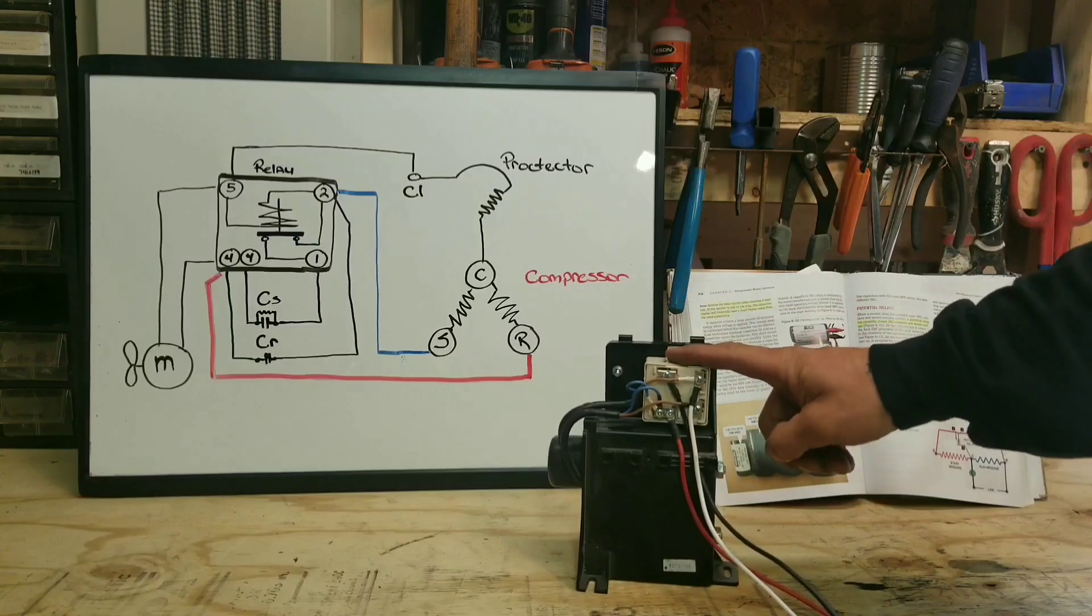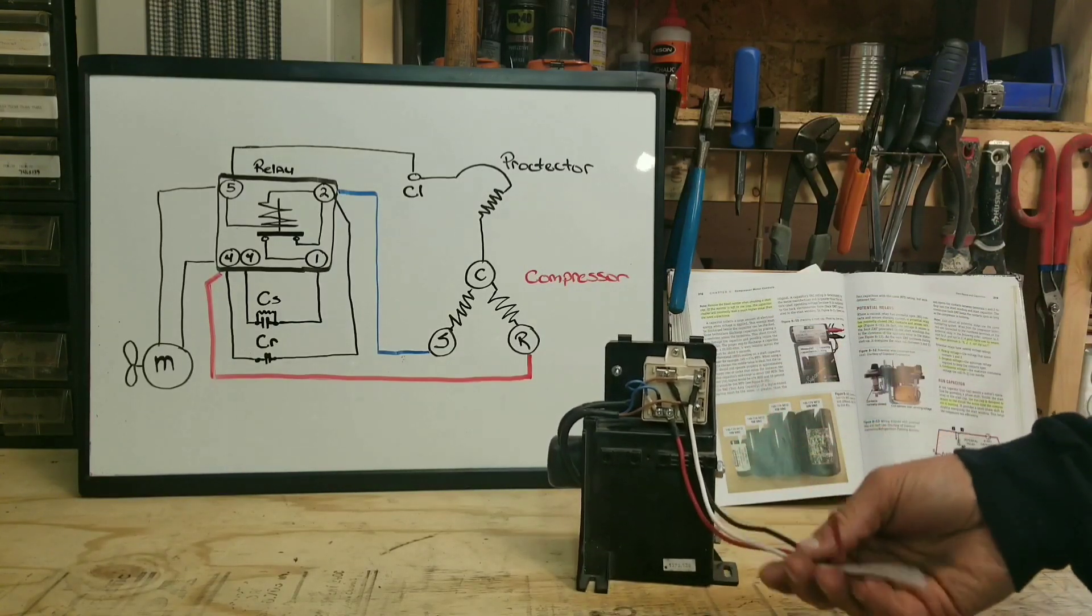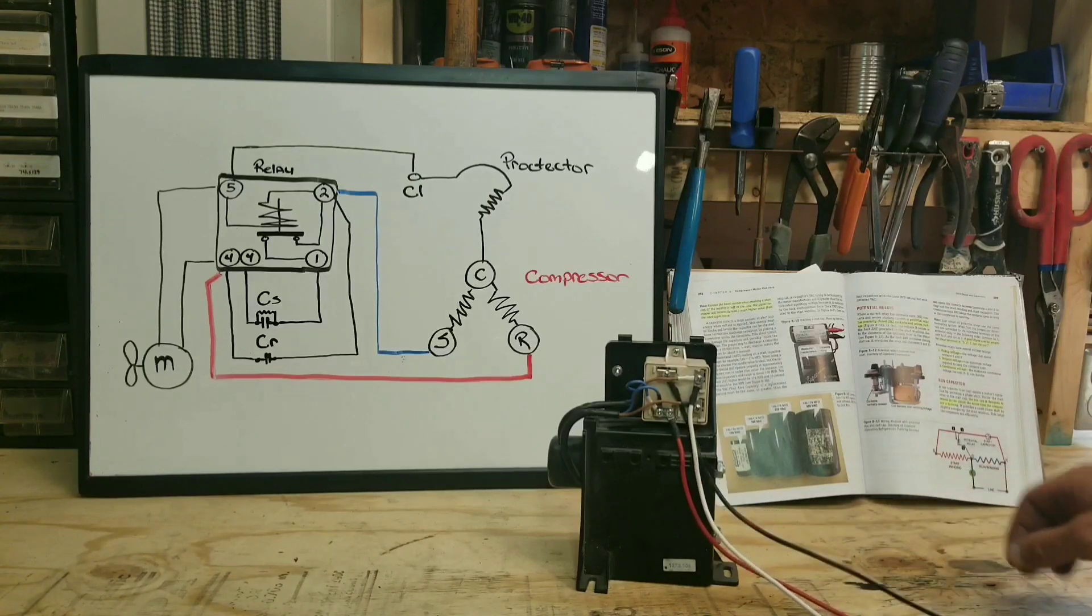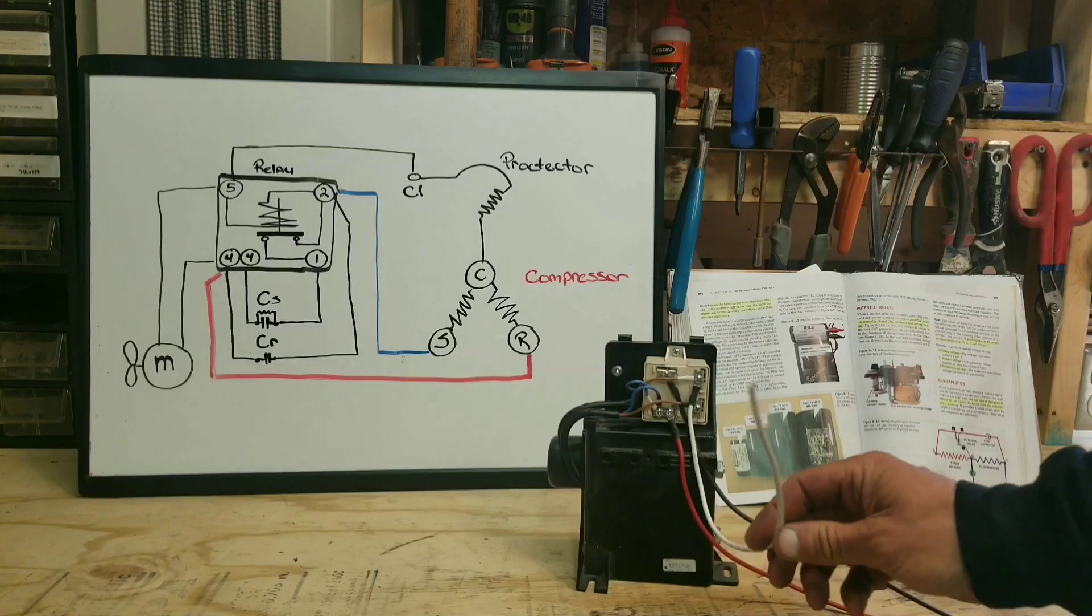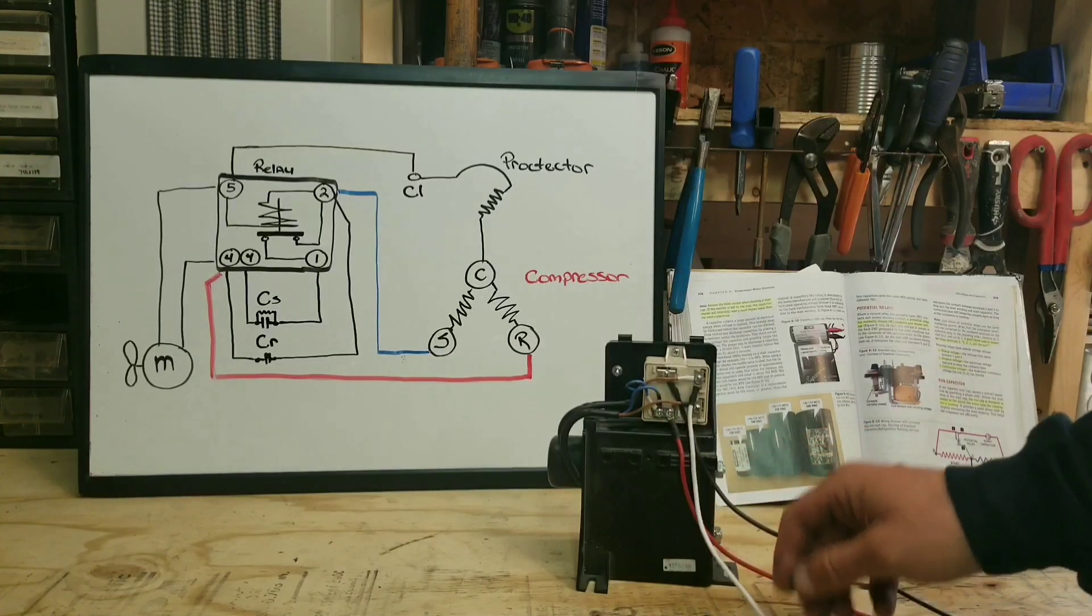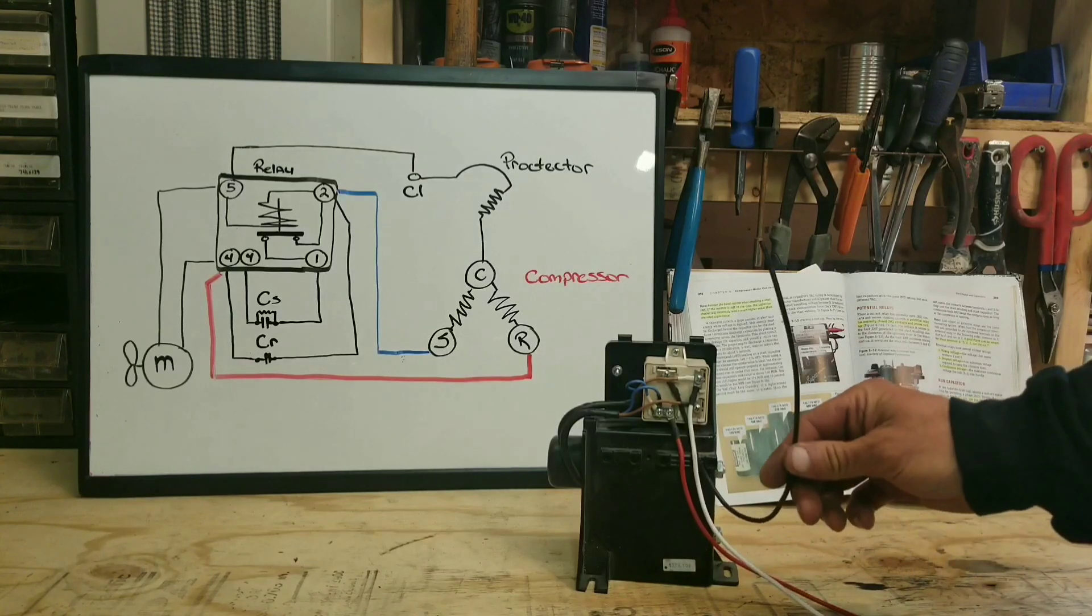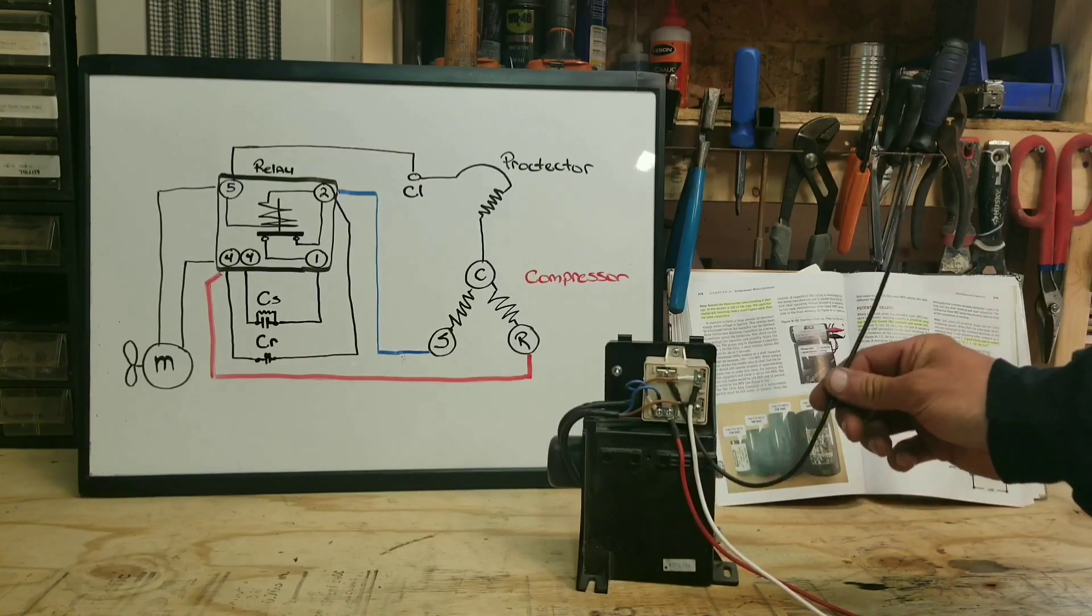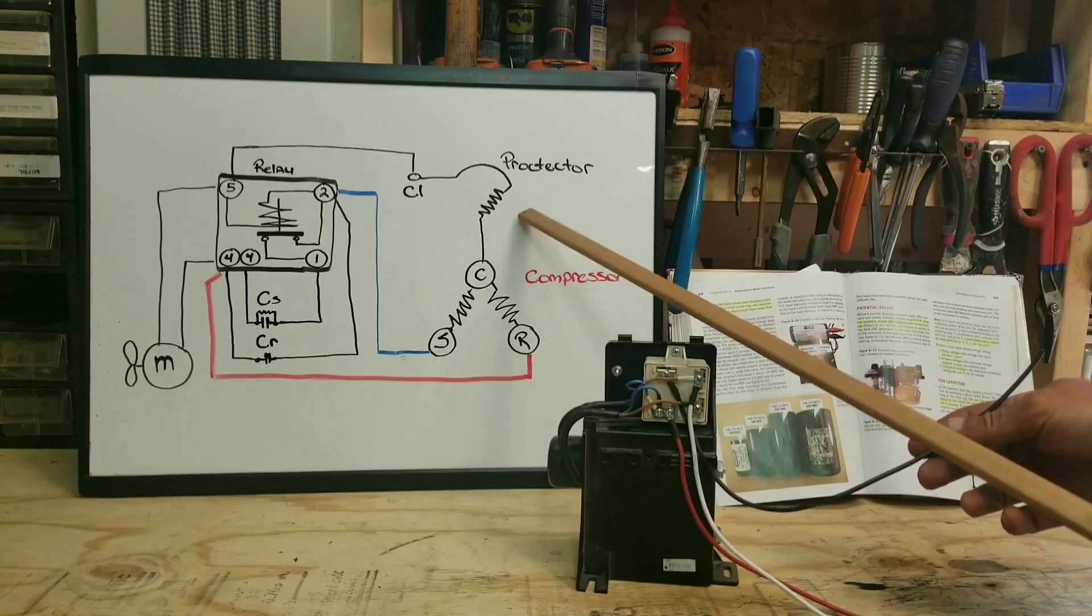So this is our potential relay. Just imagine these wires go to an invisible compressor. Red is our run, white will be our start, which is blue on our schematic because I obviously can't put white on a white board, and then black will be our common. This wire would go to our thermal protector right here.